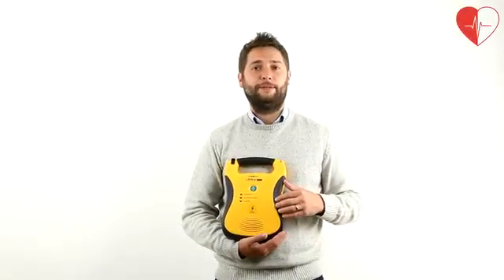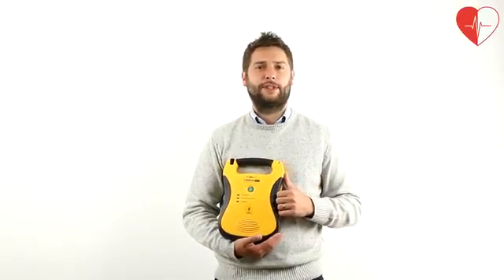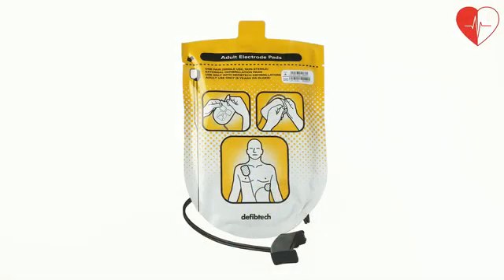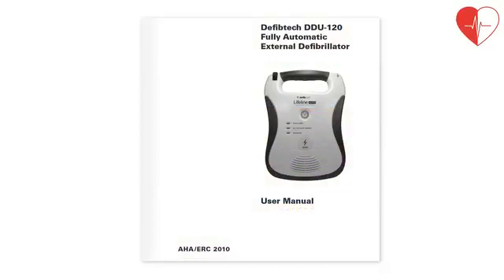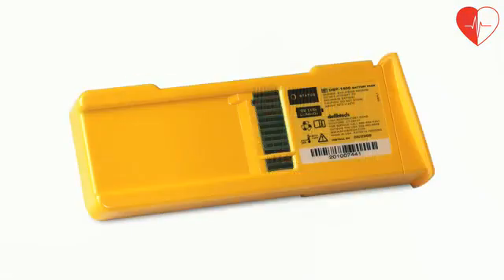DefibTech Lifeline Auto Defib Units are fully automatic AEDs that weigh just 2kg. As standard they are supplied with one pair of adult electrode pads stored in the handy pouch at the back of the unit, an instruction manual, one 9V lithium battery to power the unit's self-test function, and either a 5 or 7 year defib battery — the longest battery life available on the market.